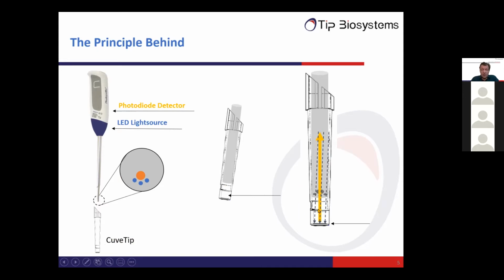And on the next slide, you have some idea about these arrows. This is the light that comes from the LEDs. It's guided by the glass fibers and then enters the cavity here of the cuvette tip. At the end of this cavity, in this region, there is a mirror, and this mirror reflects the light back. The light is then collected by another fiber and guided to the detector. If the cuvette tip is inserted into your sample, here in the middle, your liquid, then the sample enters this cavity and fills it up. And this is the area where you actually measure the absorbance or the transmission of your sample.